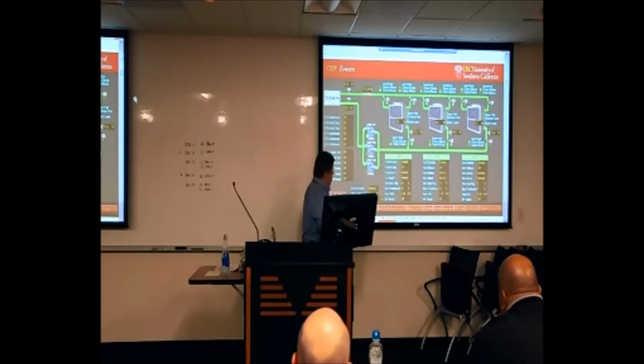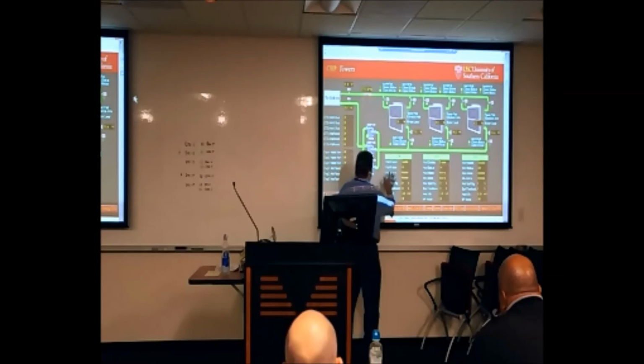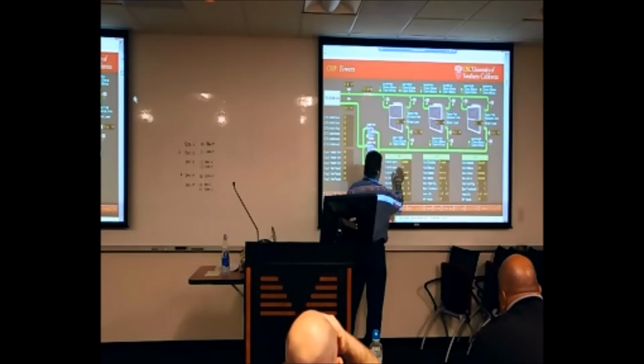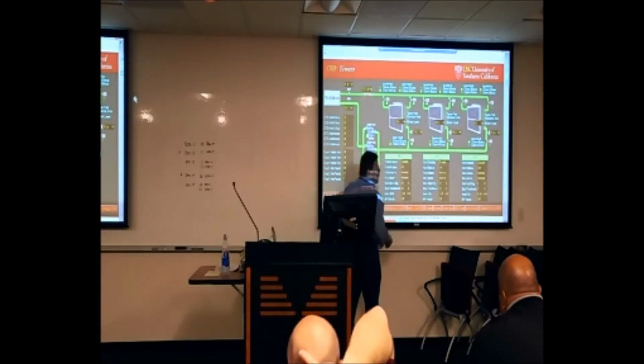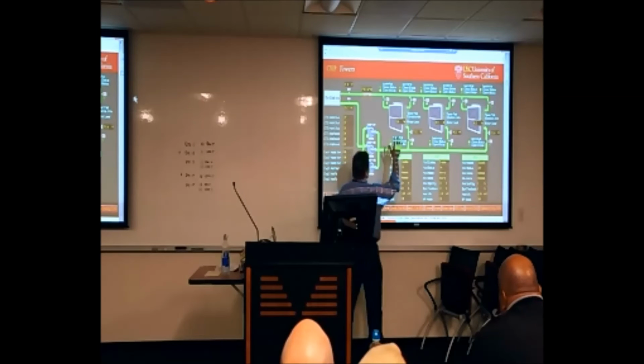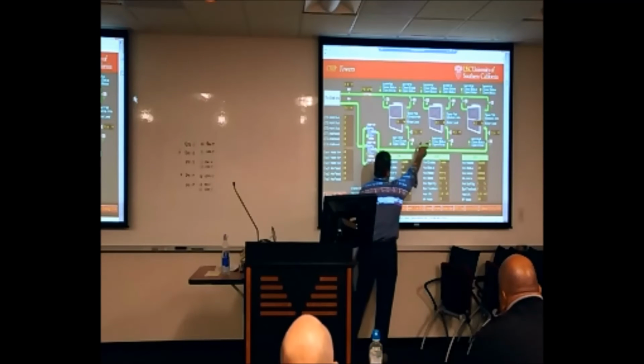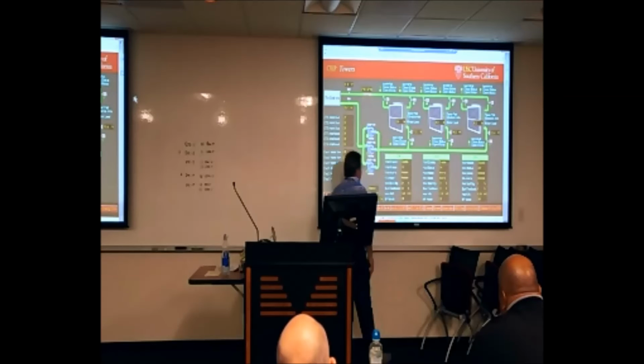And then there's also a status mismatch alarm, and that's the one we think is causing our problem. That is if Honeywell commands on the drive, and we see the VSD status not coming back, or perhaps toggling off later on after the drive is running. Then we're going to fail that tower, rotate to the next tower, and secure the failed tower.